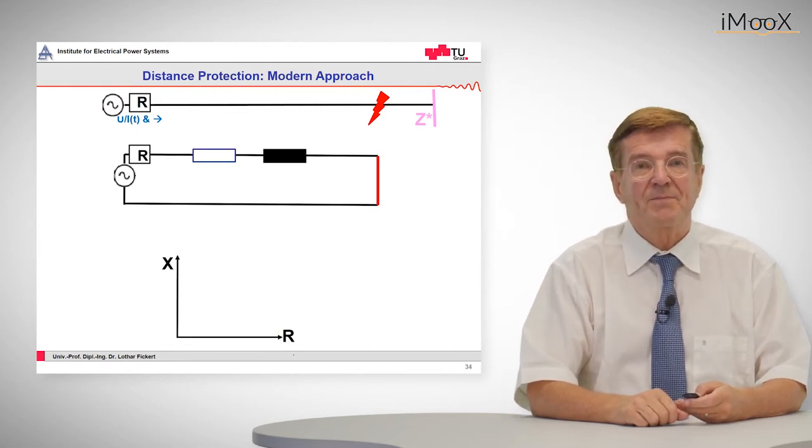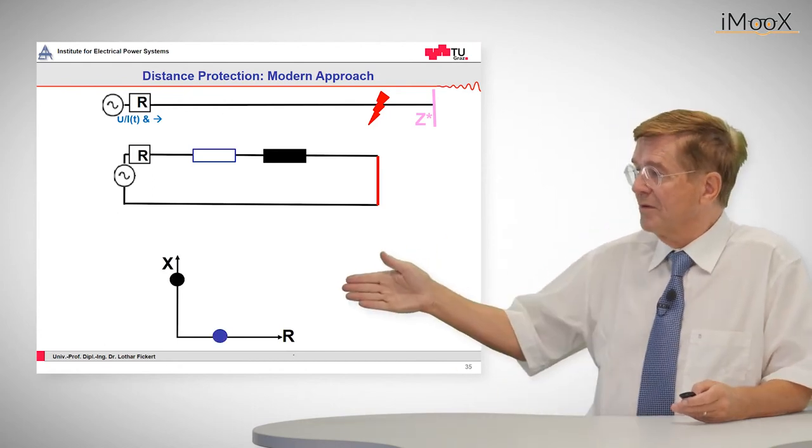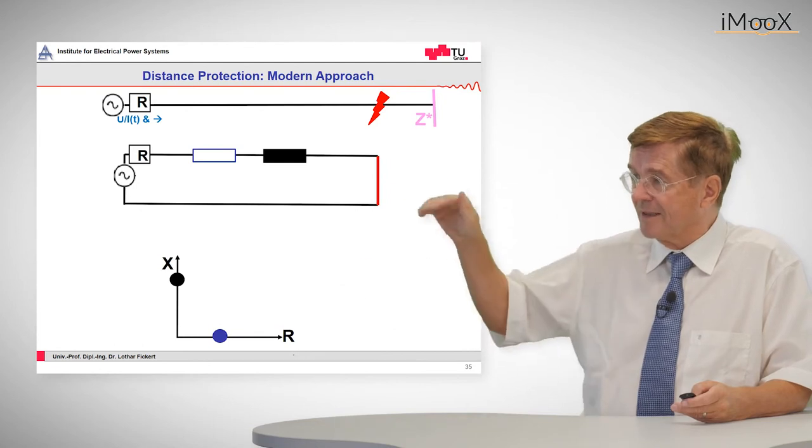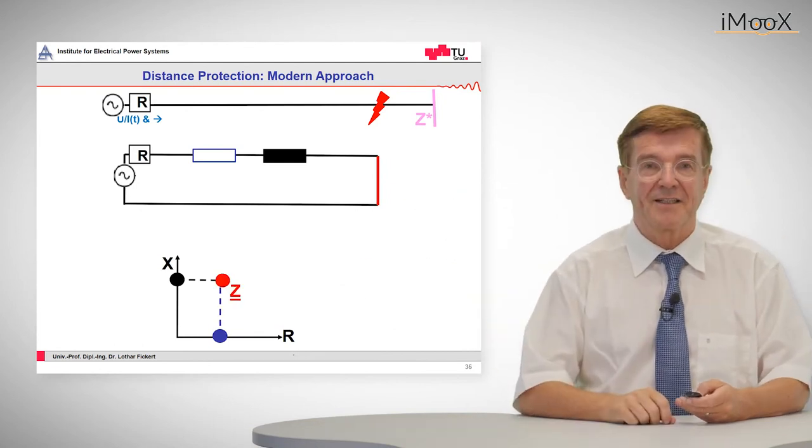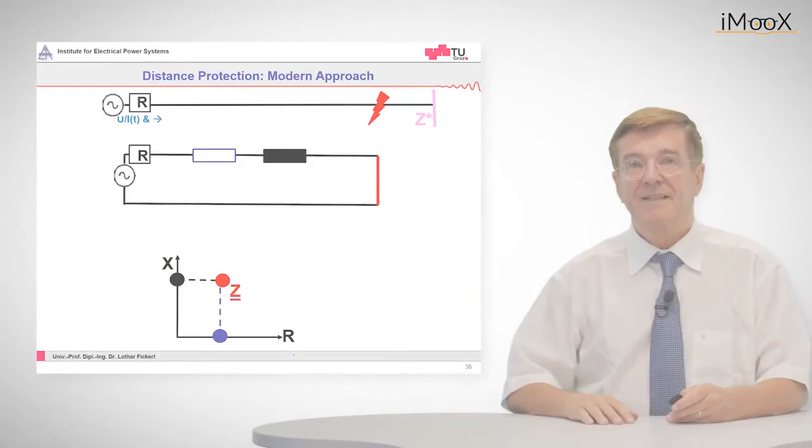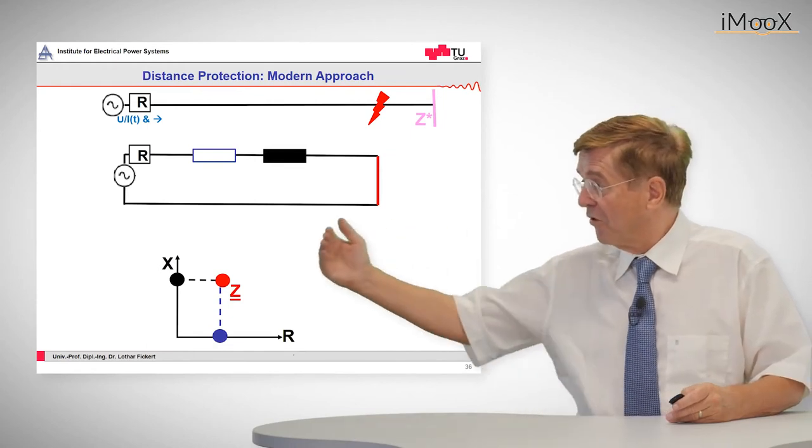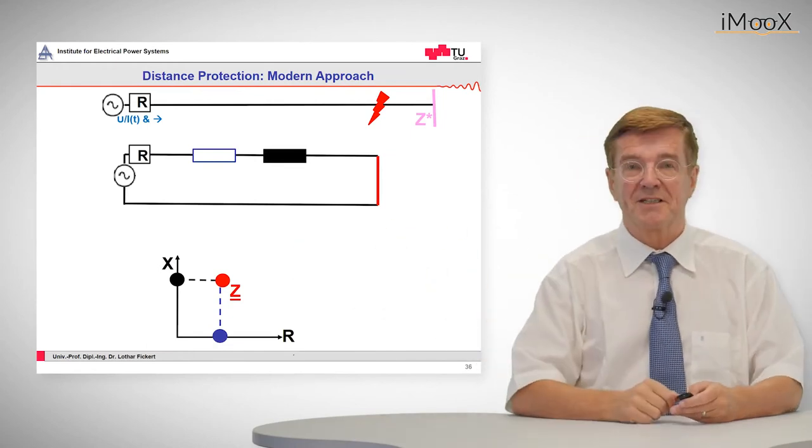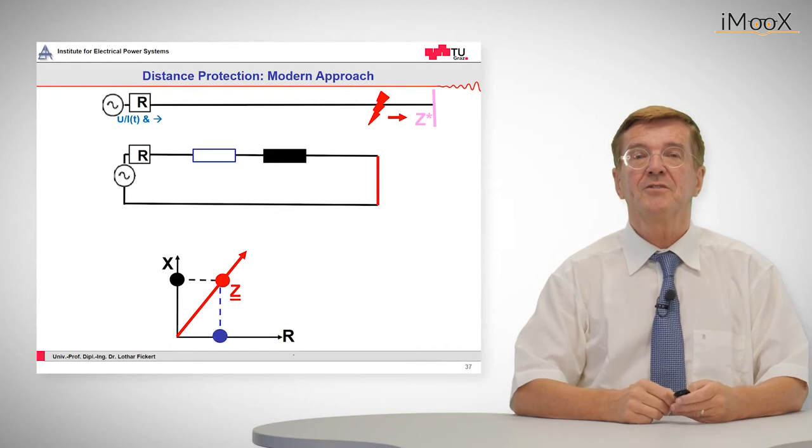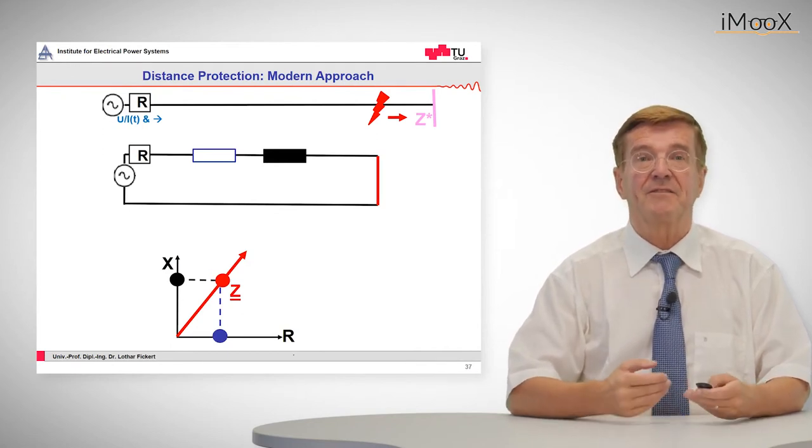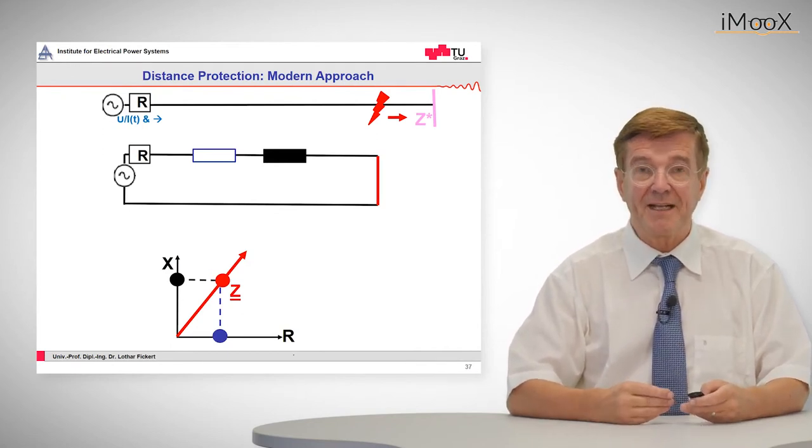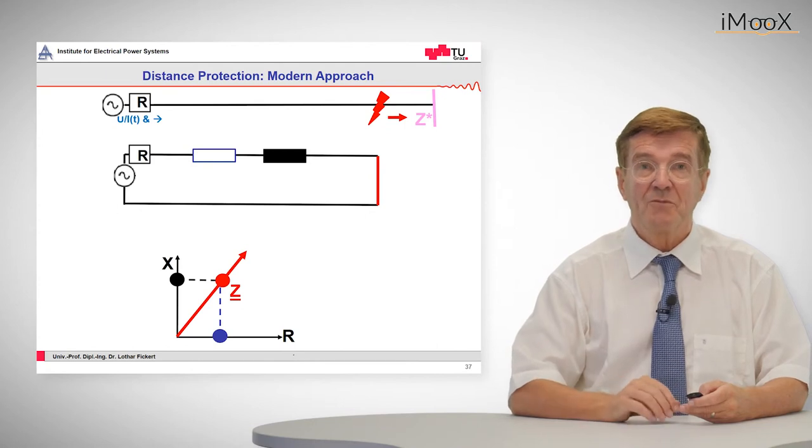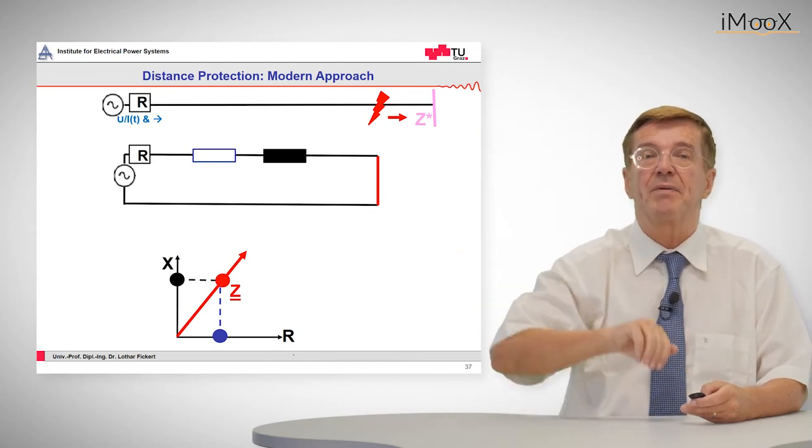Now in the impedance plane this is represented by two points, the blue is the resistance and the black is the reactance and together they add up to the impedance. Now if the fault point moves forth and back from this position then also the R and X vary but they vary in the same ratio and that means that this fault point moves along the so-called impedance line.